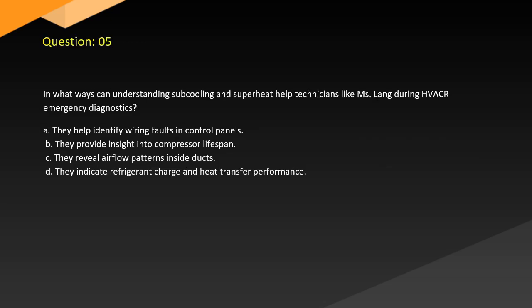Question 5. In what ways can understanding subcooling and superheat help technicians like Ms. Lang during HVACR emergency diagnostics? A. They help identify wiring faults in control panels. B. They provide insight into compressor lifespan. C. They reveal airflow patterns inside ducts. D. They indicate refrigerant charge and heat transfer performance.